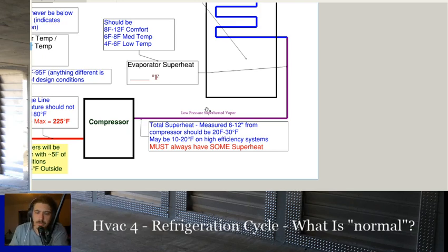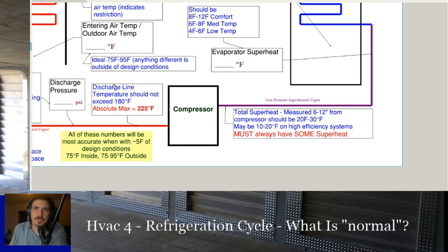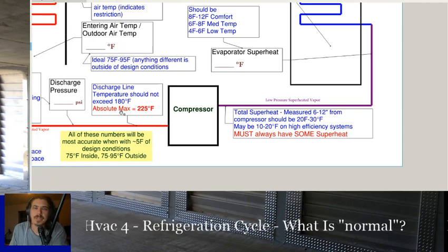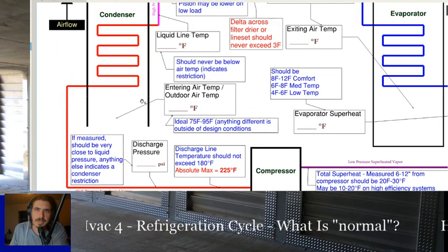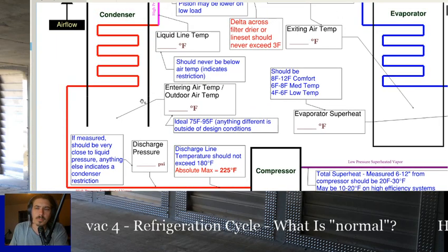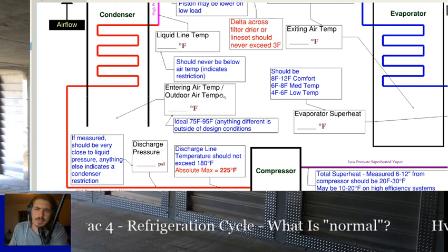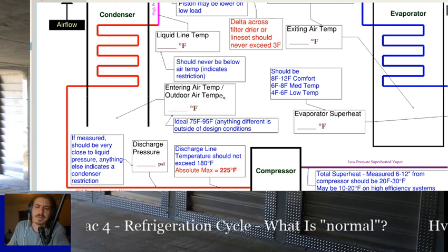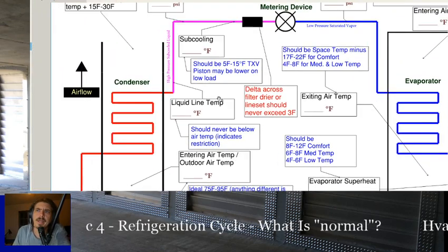So superheat's always the most important. The next most important is probably this discharge line temperature so you don't eat up the oil. And then after that, everything else is just, is it functioning properly?